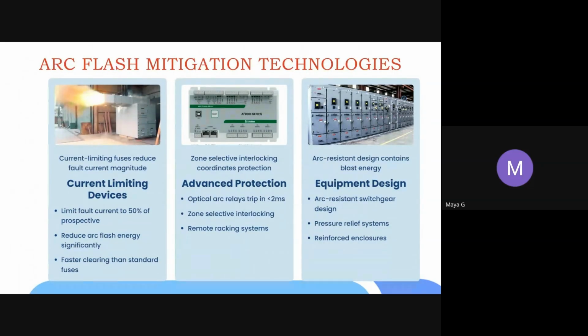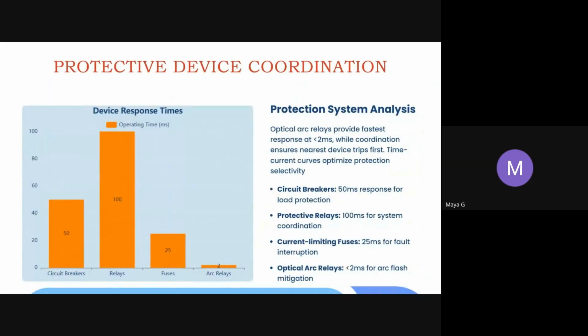So almost all these things were already discussed. Usually in the protection system, we are mostly relying on the protective relay. It will take almost 100 milliseconds for the protective relay, plus 100 milliseconds for the system coordination. Whereas the best option is the optical arc relays, which will operate within 1 to 2 milliseconds when an arc flash occurs.